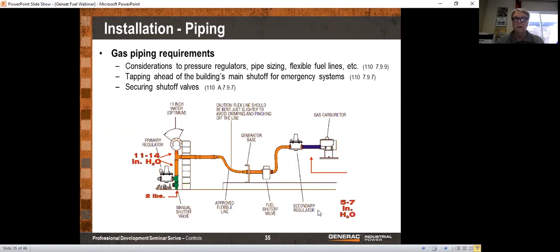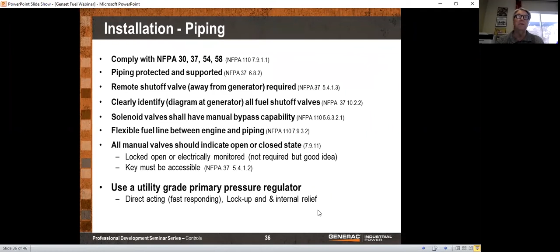These are some of the piping requirements. Pretty much what you would expect: protect the piping, have a shut-off valve so that you can shut it off if necessary, have diagrams, and so on. We recommend actually padlocking the natural gas valve in the open position, because our biggest problem with natural gas generators is somebody goes out there and turns off the valve.